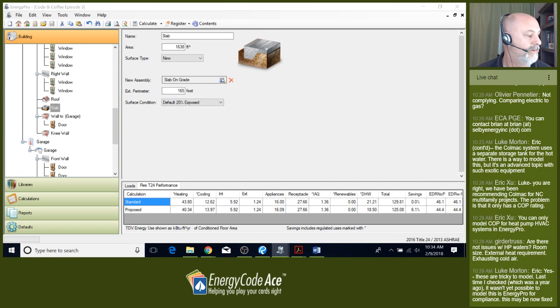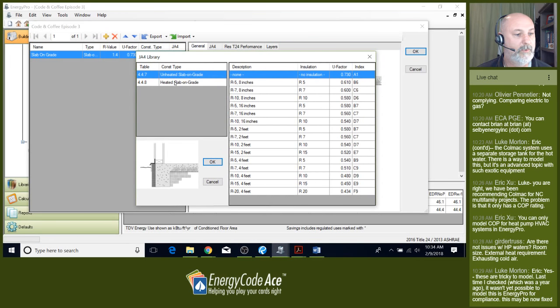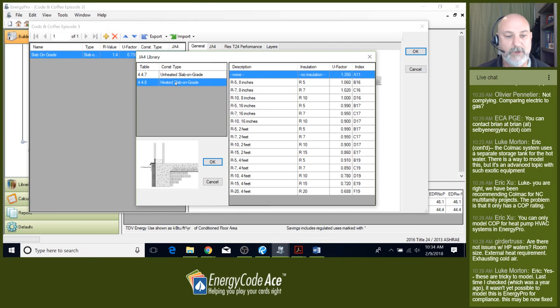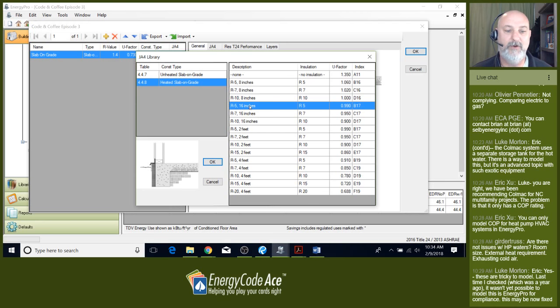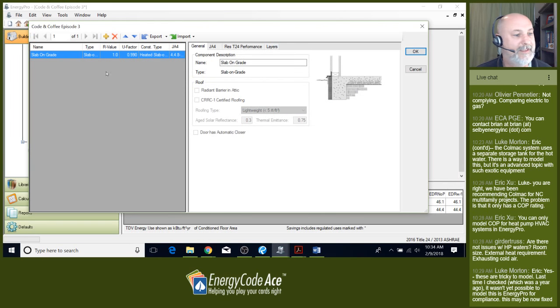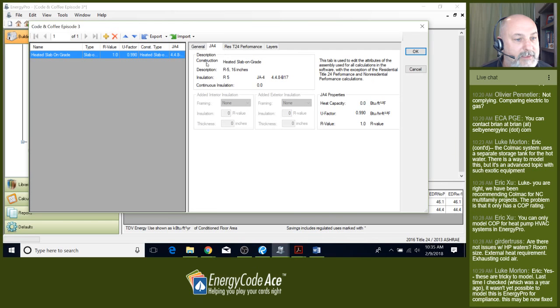We need to import a heated slab using JA4 table 4.4.8. The standards require R5 perimeter insulation at 16 inches in depth or the bottom of the footing, whichever is less. We need to select at least this R5 16-inch value — anything less will generate an error. I'm changing from a slab on grade to a heated slab on grade, construction per the JA4 table: heated slab R5 perimeter 16-inch depth.